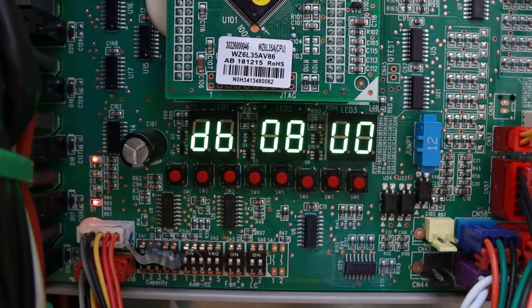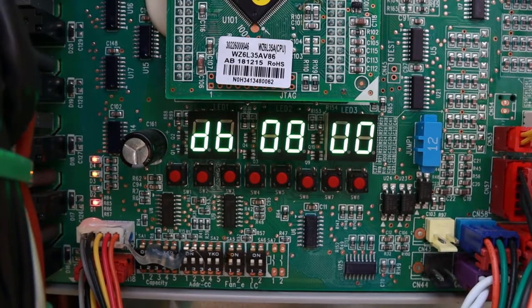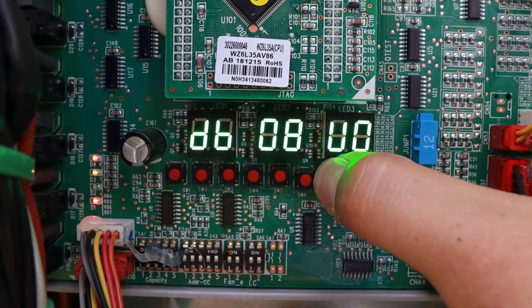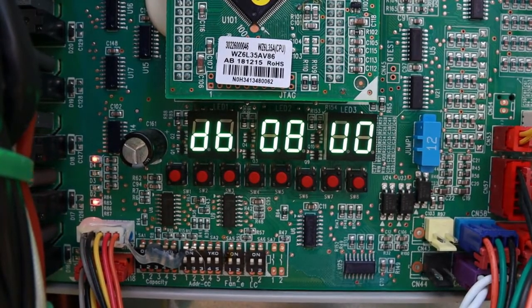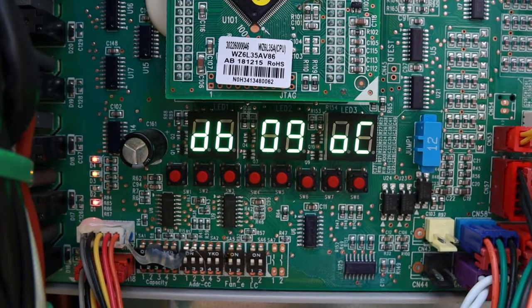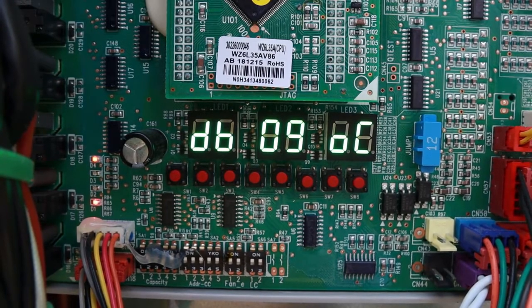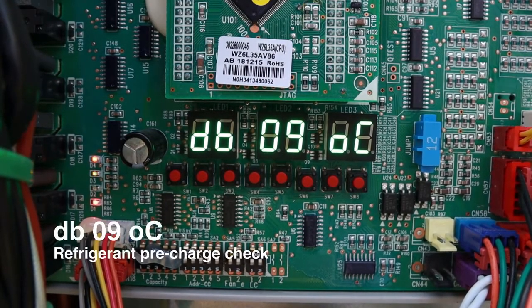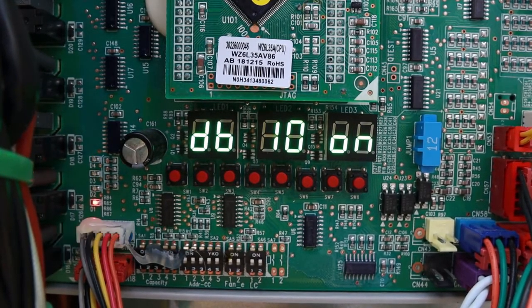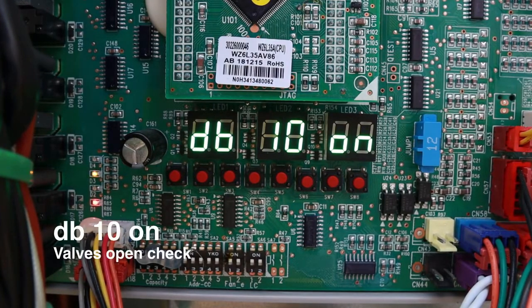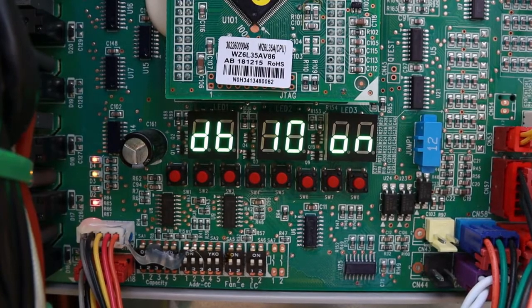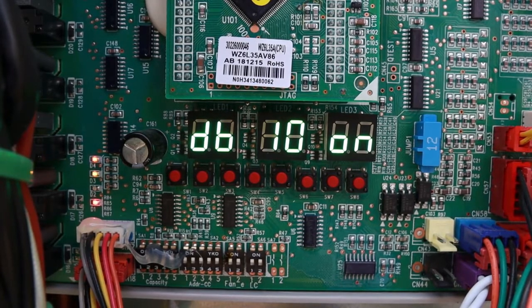Because this system has been commissioned before, I'm able to press confirm SW7 to move up to the next step. But in your case, if it's a brand new unit, just wait the 8 hours, and then the system will automatically jump to step 9. Step 9 is a quick refrigerant charge check, and then it will jump into step 10. On step 10, the system is checking that the valves are fully open. You will hear the compressor kick on, as well as the fan motors, and the system will run for a few minutes.